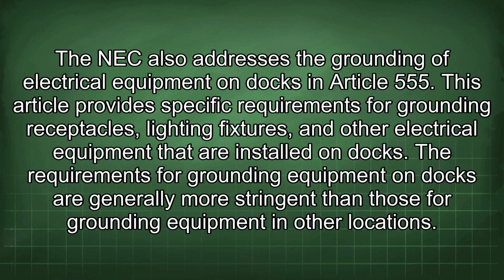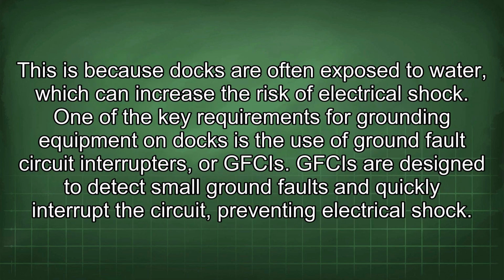The NEC also addresses the grounding of electrical equipment on docks in Article 555. This article provides specific requirements for grounding receptacles, lighting fixtures, and other electrical equipment that are installed on docks. The requirements for grounding equipment on docks are generally more stringent than those for grounding equipment in other locations. This is because docks are often exposed to water, which can increase the risk of electrical shock.